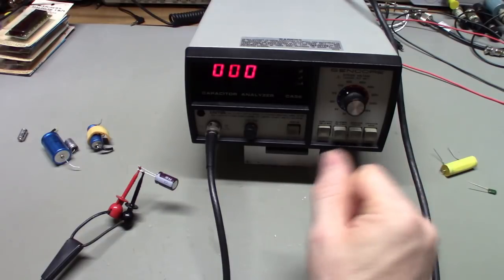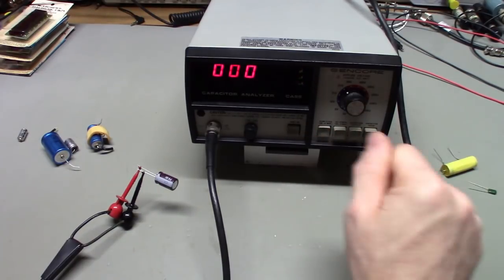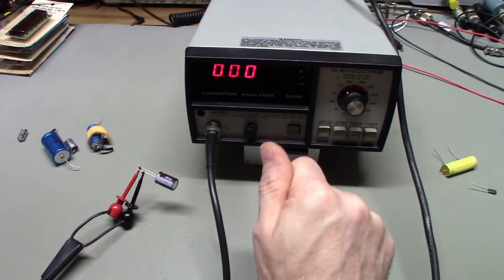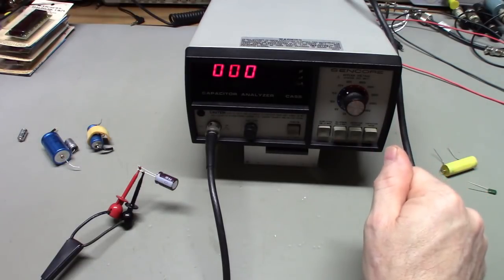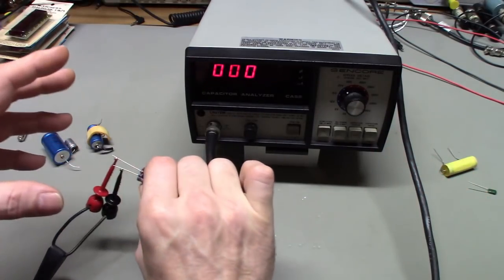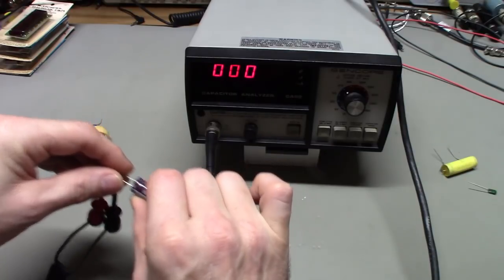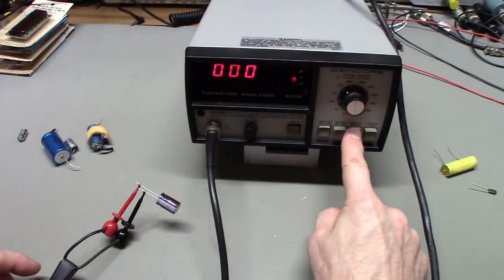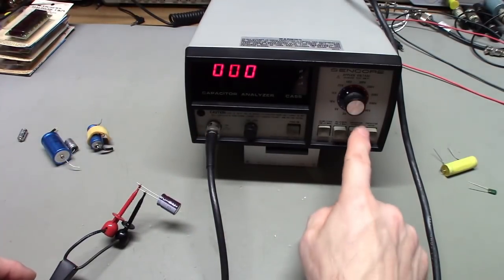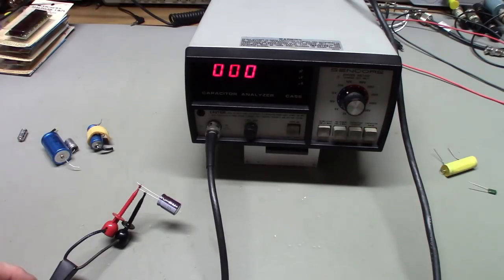Some of them are spring loaded. So some of them, if they don't have that spring-loaded switch, you can leave it in the leakage position so there's voltage there. You could then mistakenly come down here and grab this thing and electrocute yourself. This one, again, has the spring-loaded button, so as soon as you release the button, it shorts out the terminals here and discharges the capacitor.